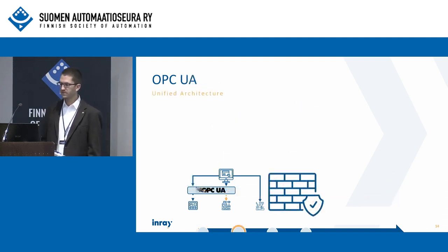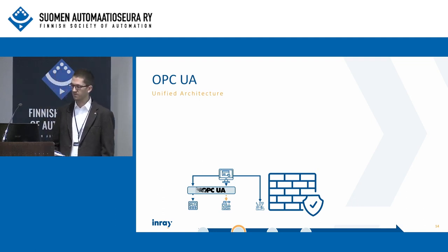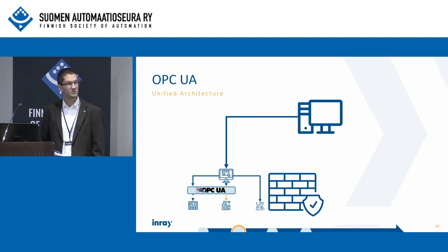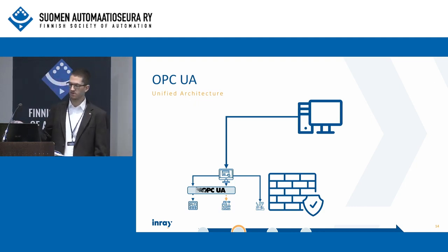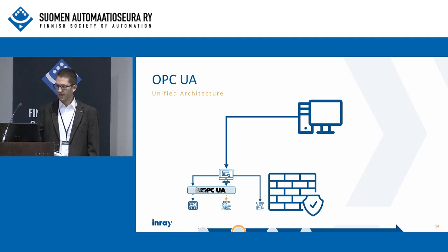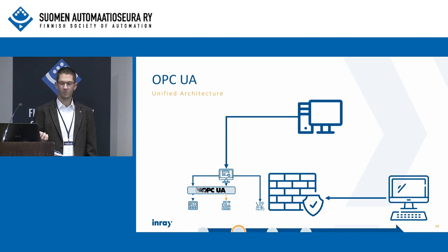This is where OPC UA comes in to solve all this and so much more. I'd like to just name some of them. Localhost equals remote host, so there's no difference between connecting from an OPC client to a local OPC server instance or to a remote instance. It is platform independent, so it runs on Windows and on Linux devices, and connecting through a firewall is easy, it's just opening up one port.